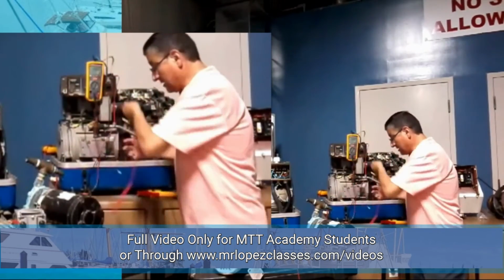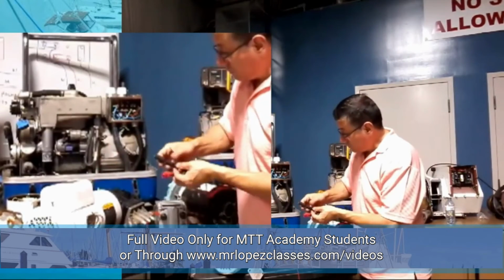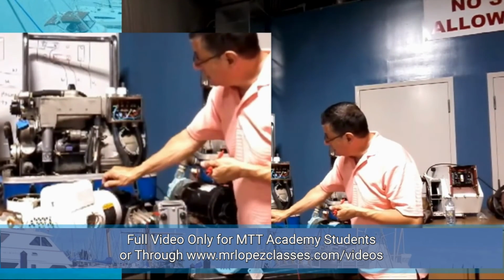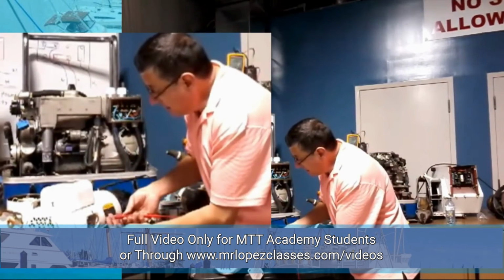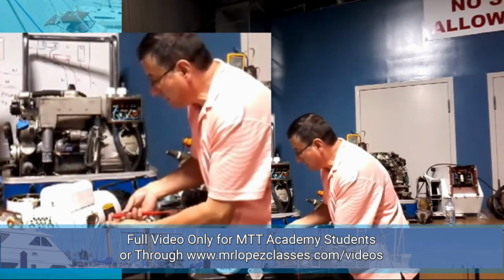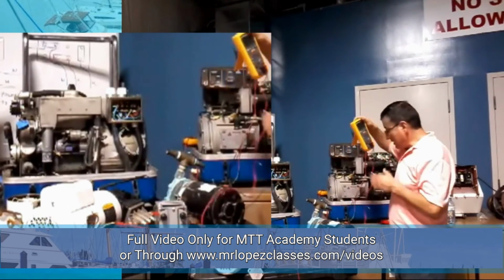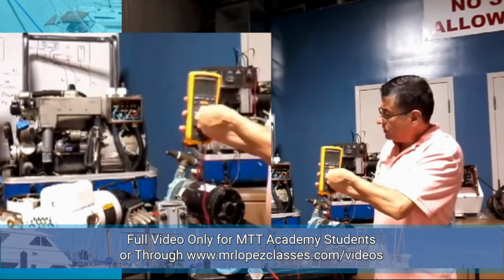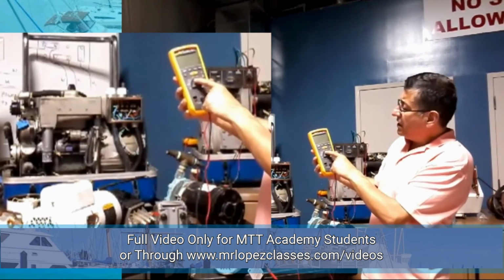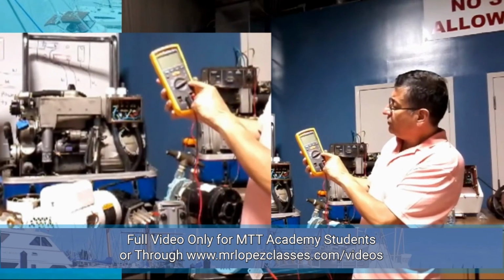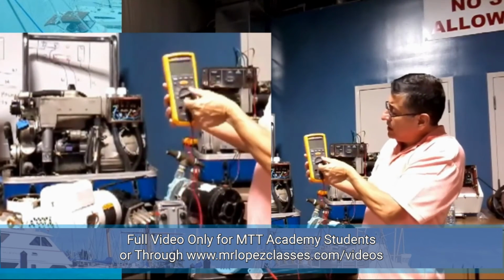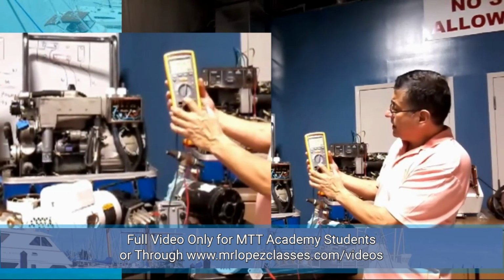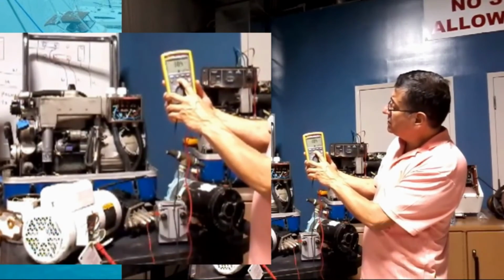For example, I am going to check this three-phase motor with this digital megohmmeter. I have the ground here, and I have the phases here. I am going to check phase number 1. I am going to show it to you. I can apply 1000 volts, 500, 250, 100. I am going to apply 500 volts, and I am going to apply the test. After some seconds, it is 543 megaohms.